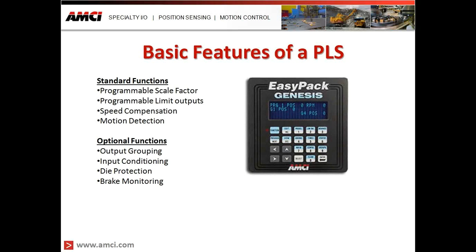Some basic features of a PLS include a programmable scale factor, allowing you to set the counts per turn of the encoder or resolver anywhere from 2 to 1,000 counts per rotation. This gives you either fine precision or, if you set it to 360, you can relate the position to simple degree positions.